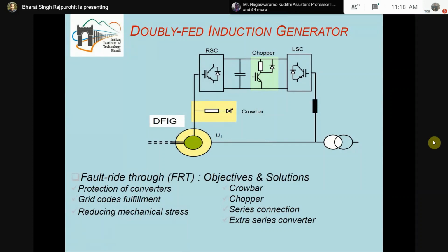During normal operation, the chopper is not active and is not in operation. It is simply disconnected from the DC link side. It is not doing anything. As soon as the requirement is there, a signal comes to this chopper, and then the chopper gets activated. So this is how it is working.